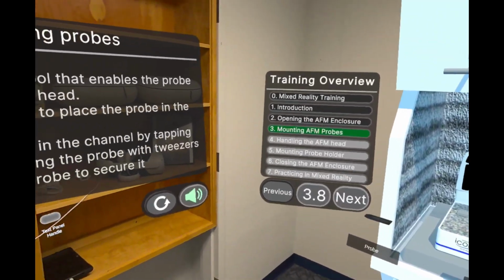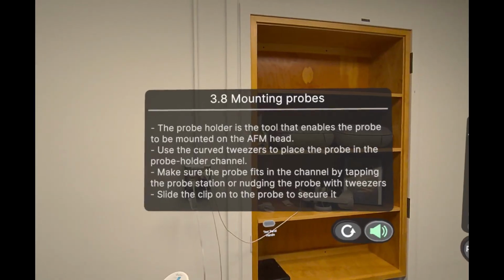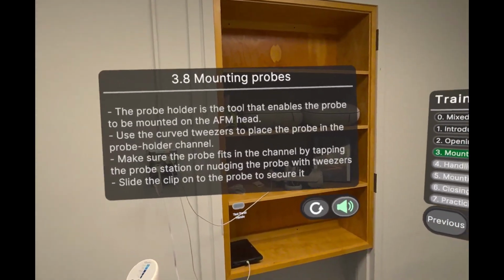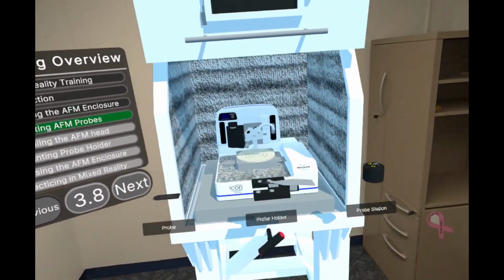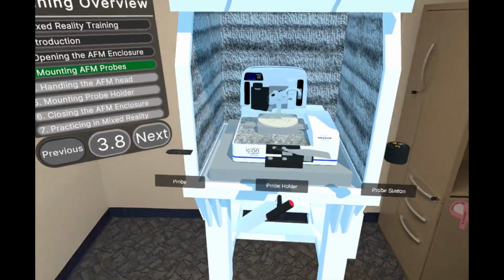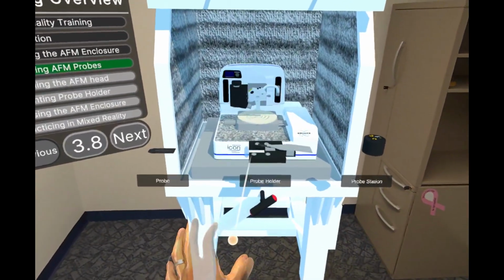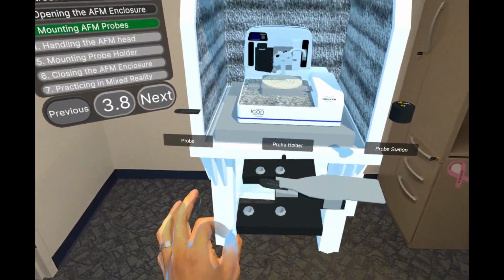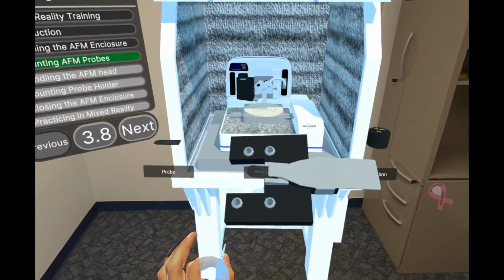Mounting the probe. There are 2 tweezers in each AFM enclosure. The straight flat ones are for samples. The curved sharp ones are for mounting the AFM probes. Please do not use the curved sharp tweezers for sample handling.